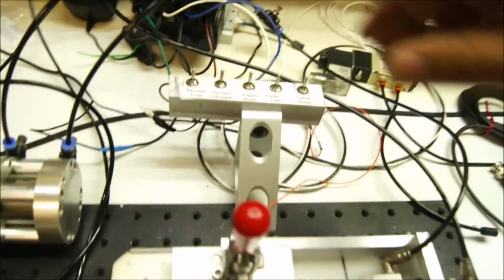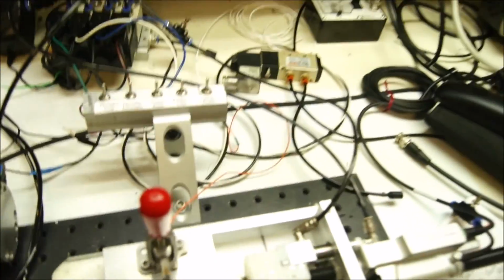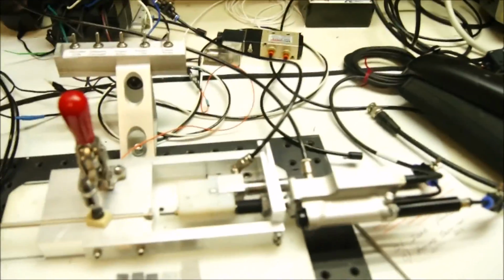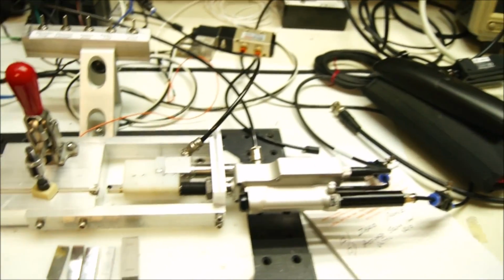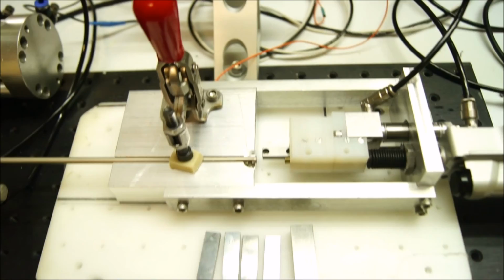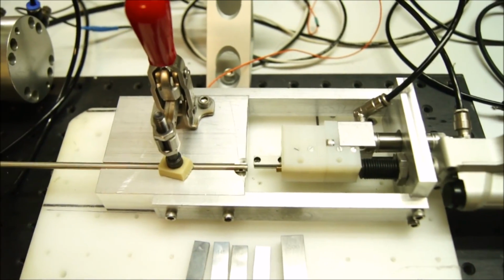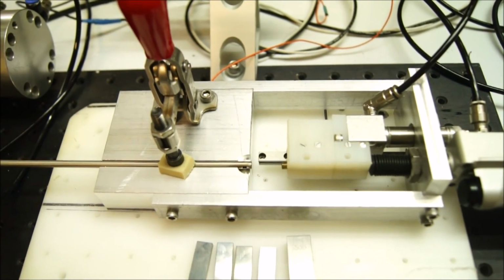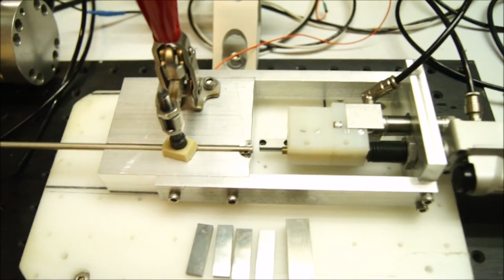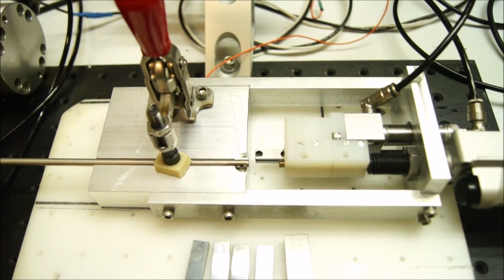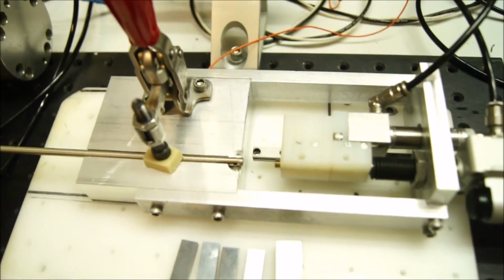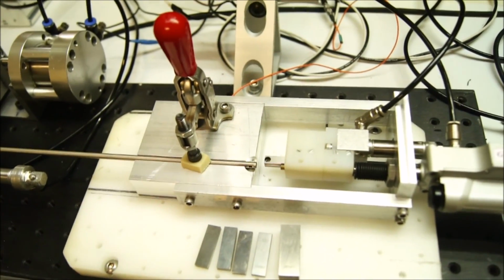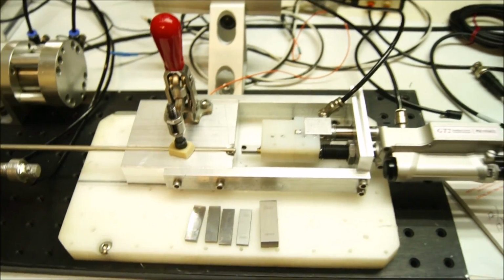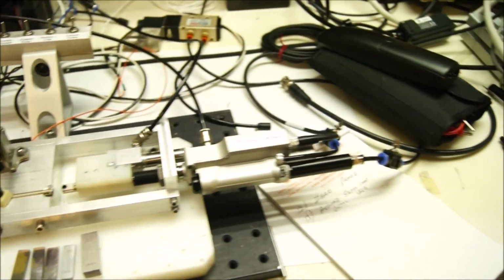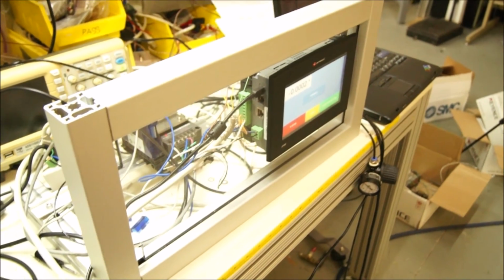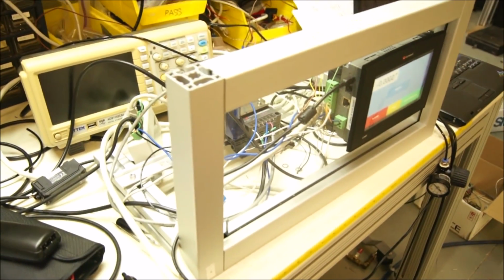We're activating everything manually to verify that everything works before tying it back to the PLC. The PLC, however, will run the first sequence, which is to set the pusher just proximal of the tip of the cannula. That's also something that was new from the original concept. So we tested the code required to get that done, and we're going to be demonstrating that in a minute. Okay, so I'm going to set this thing up to run, and then we'll get back to it.